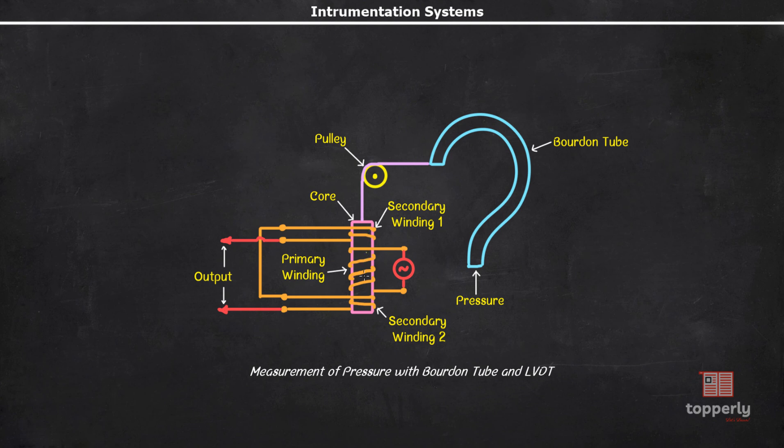So whenever there is displacement at the tip of the Bourdon tube, the amount of core inside the winding will be different. And as a result, we get an output voltage as a function of the input pressure. And since this output is electrical in nature, it can be fed to a digital instrument. So in this case, you can see that the sensing of physical quantities is done by this block. So this element, which is directly coupled to the system under study, is known as the primary transducer.